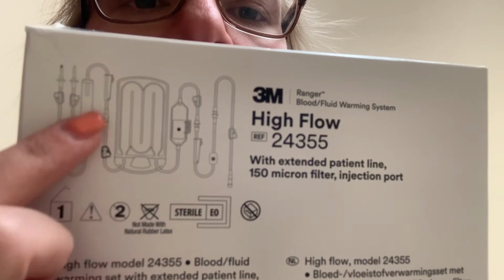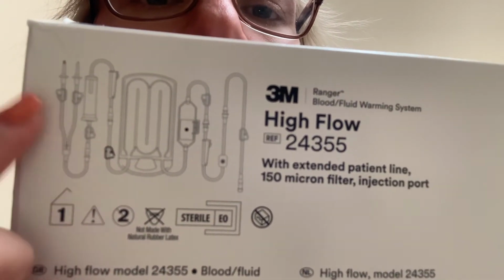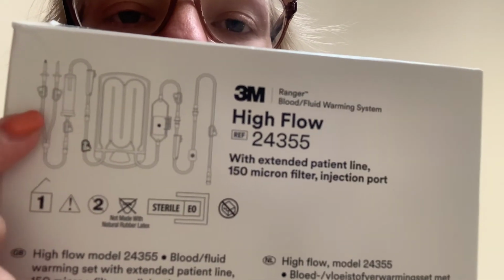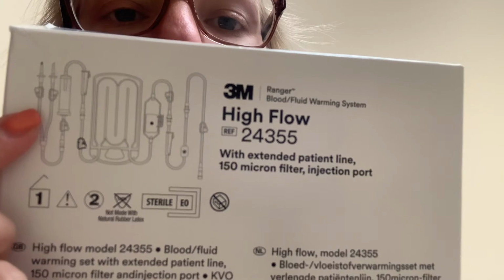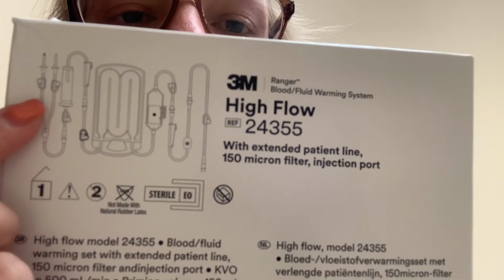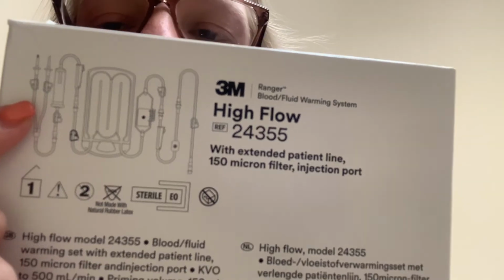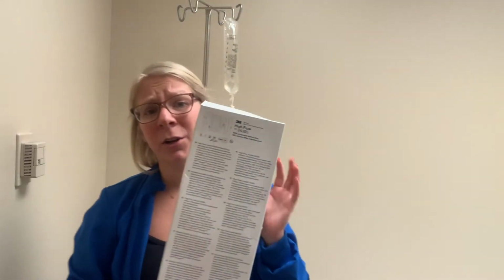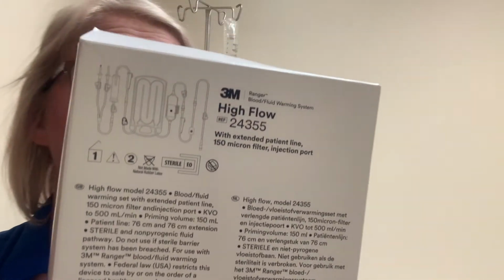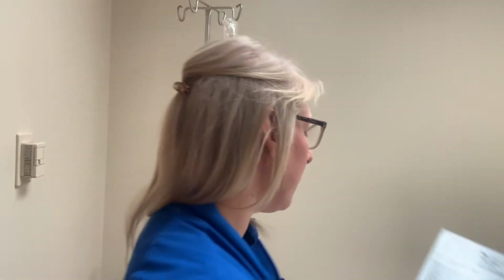If you look at this picture here, it actually comes with the tubing, and that goes to the actual bag of fluid or bag of blood that you're going to be hanging, and it has two ports there, so you can hang two at a time. This also does have a micron filter, which means that you do not need an extra filter for the blood. So it's a two for one there. And again, these are the ones that you're going to be using on your very, very critical patients that need blood products super fast or that you need them warmed super fast. And it inserts just like the other one. So let's go over insertion real quick.